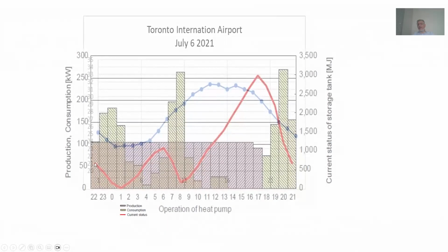So if you see the water there, you've got a demand. The water is going down, then you charge the system. Then you meet your demand. It goes down, and then you charge the system back again to meet your demand. So again, the storage is the key in this typical application, where we want to run the machine for the maximum time, like 16 to 18 hours, to make sure that we get the required hot water, but in our tank, which is charged by the machine, and the tank is the one supplying the hot water to the facility.